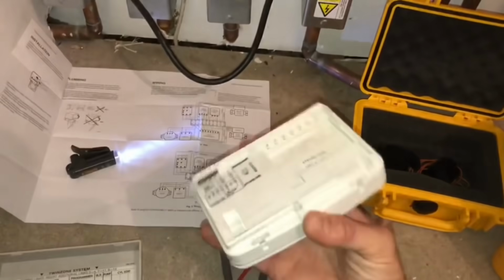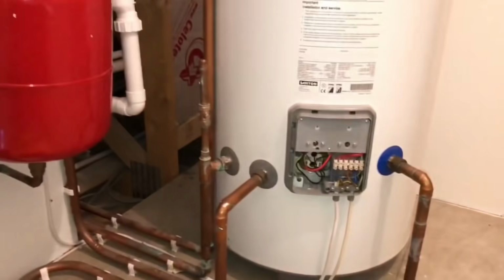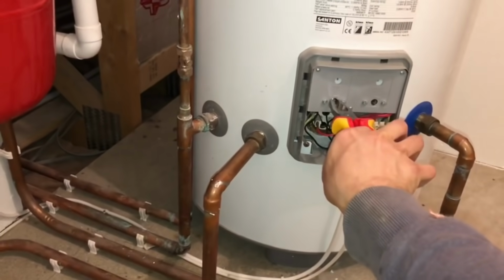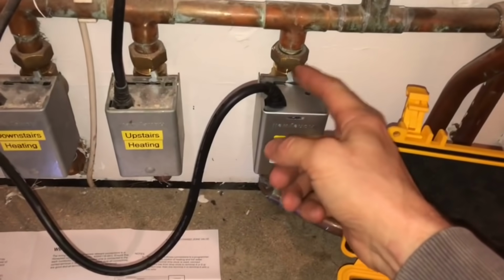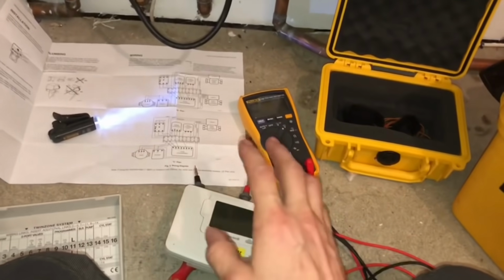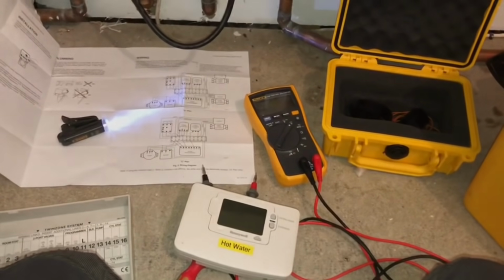So I've pinpointed this to the programmer. All I've done is put a link wire in to put a live feed down, which then goes to our cylinder stat. So if we put a demand on by turning the cylinder stat up, that's energising the zone valve, which is opening, and then the power's going to the boiler for the boiler to fire up. It's just a process of elimination. Always starting at the programmer.